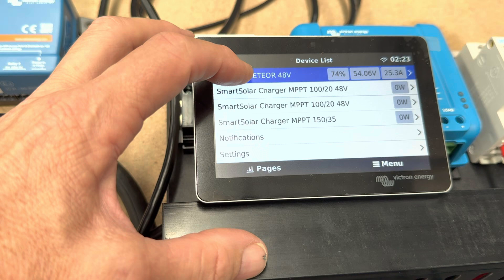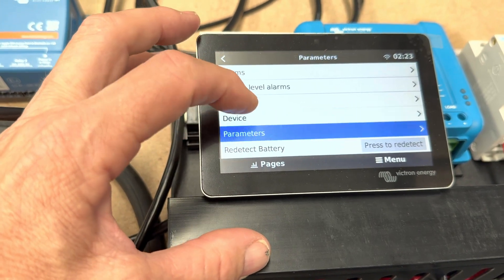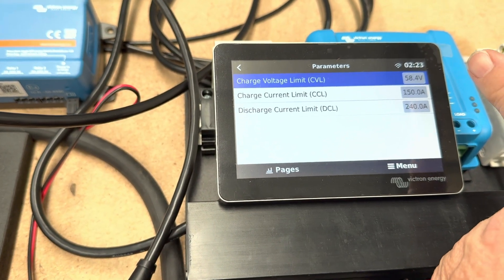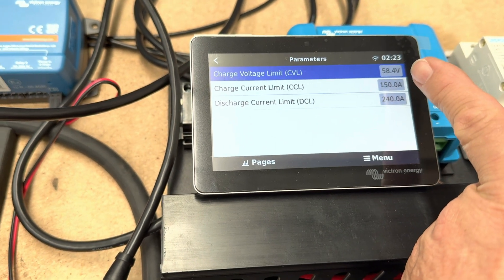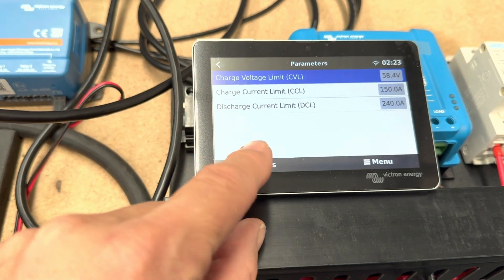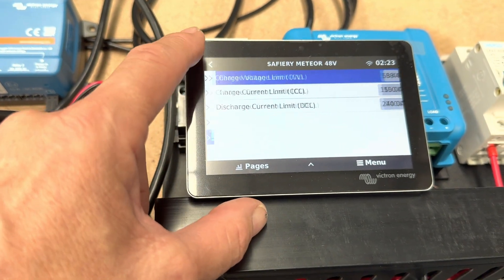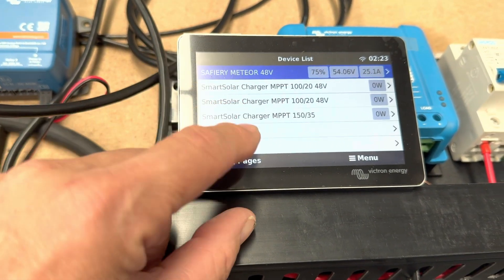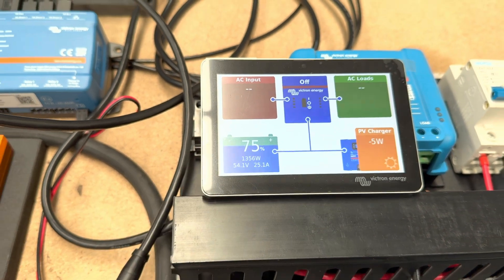There's the Meteor battery and if I go down here into parameters, you can see we've got the charge voltage limit here and we've got the charge current limit here, 150 amps. The batteries over there are suitable for 150 amps and that's the charge limit that we've got on it and that's the power coming in.